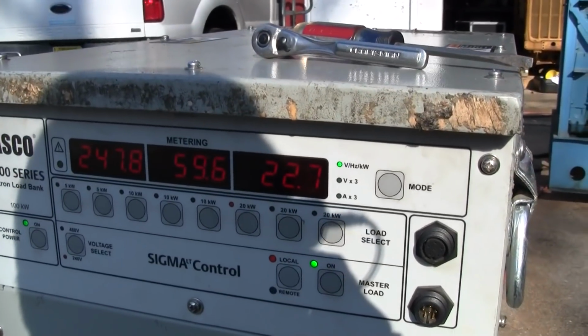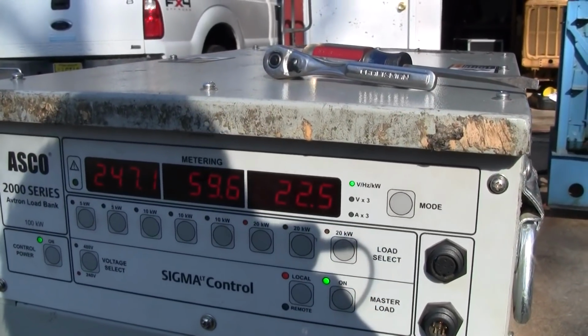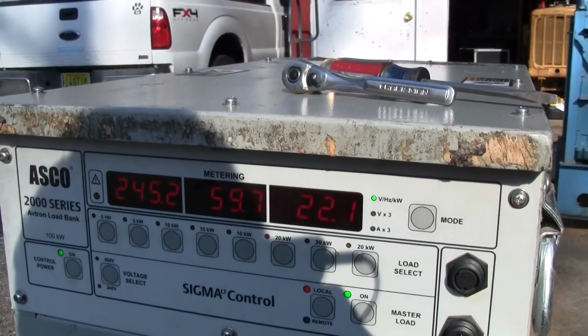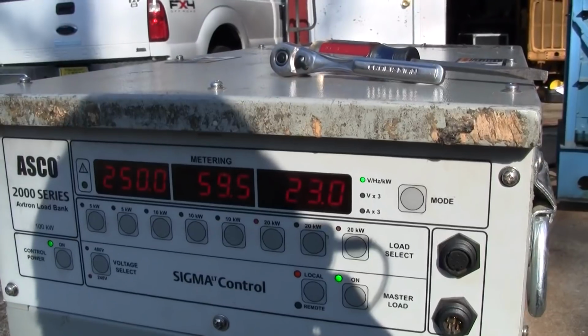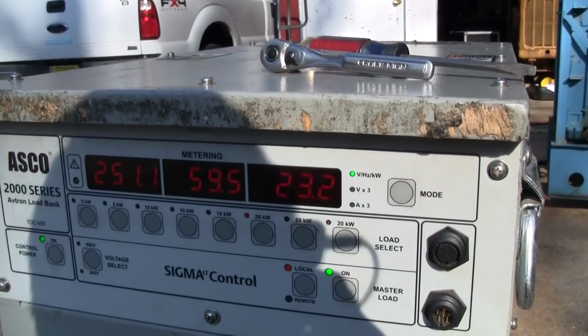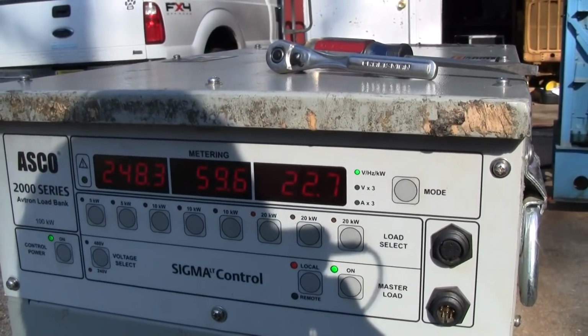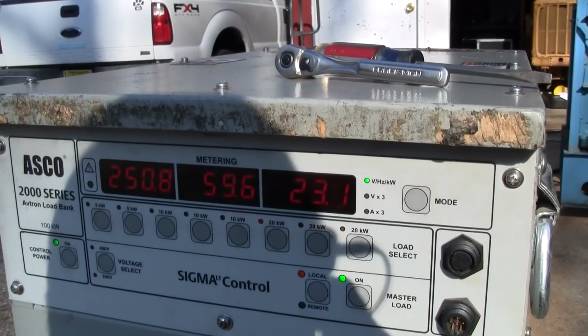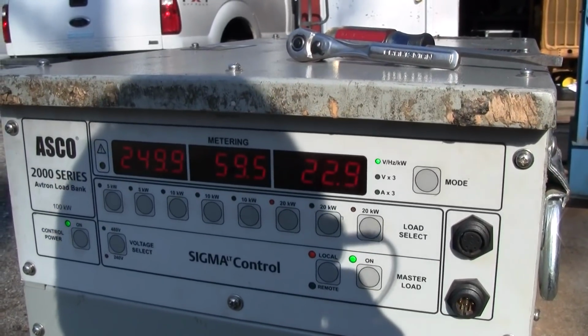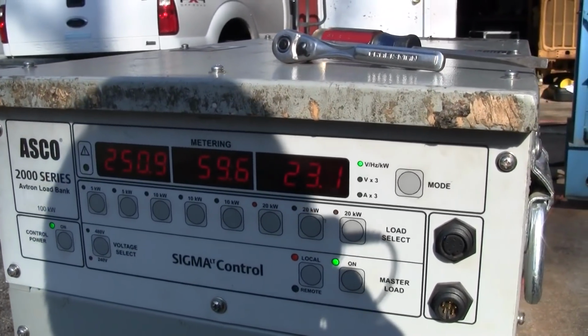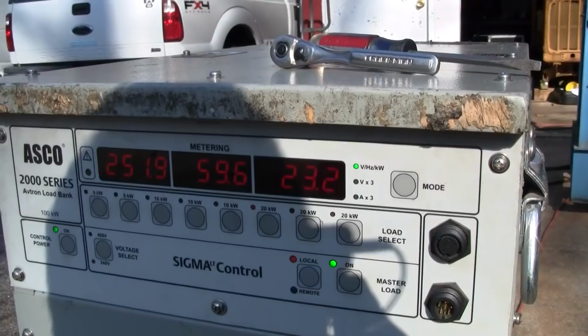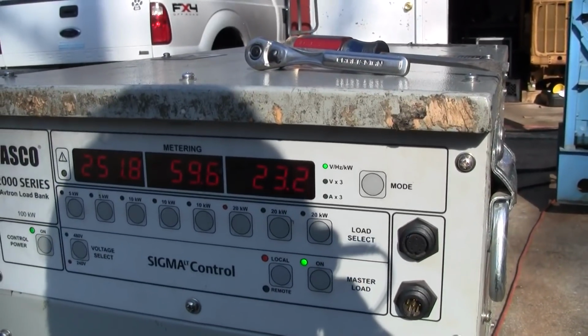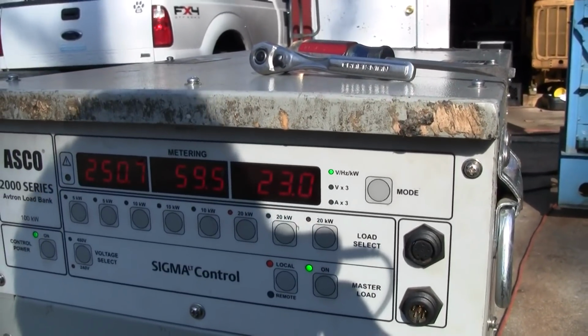That's a bad drop. I think we're still in the same boat with our governor issue. We dropped 2 cycles per second with not even a 50% load, well, about 50%, 23 kilowatts. It's a 45 kilowatt unit.